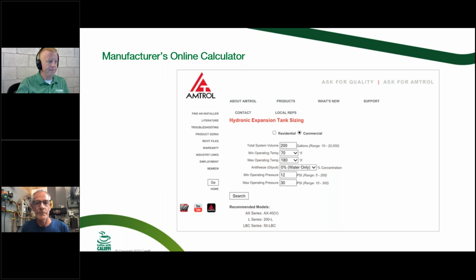So yeah, these are the expansion tanks, and every manufacturer has one of these. What I did see on the Wessel site today is they actually have a compression conversion calculator. So if you put in the size of your 30-gallon compression tank, and then input all this information, the temperature and the pressures, it'll give you the conversion to a diaphragm type.